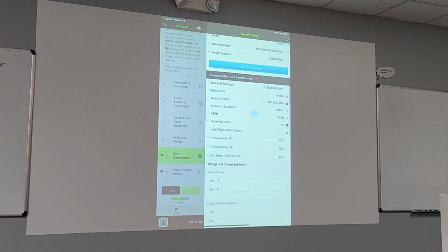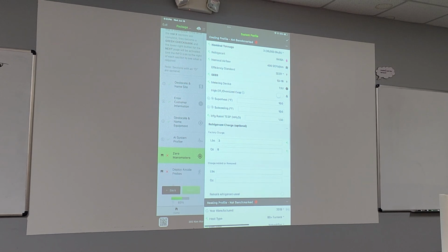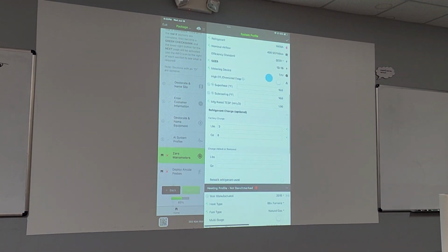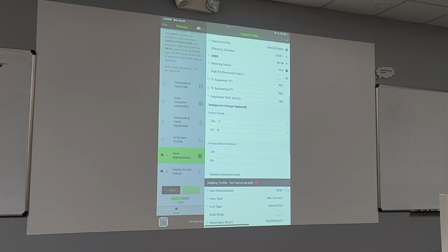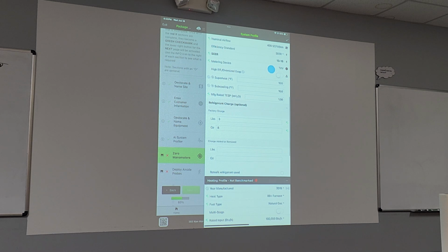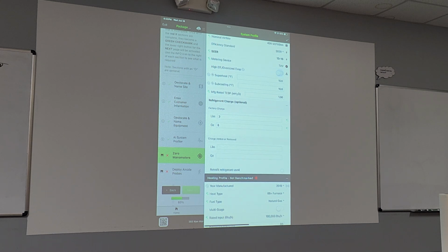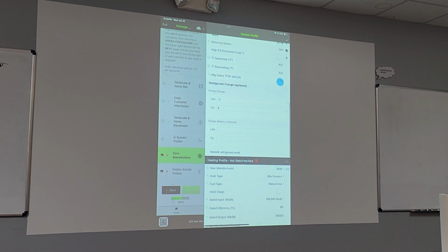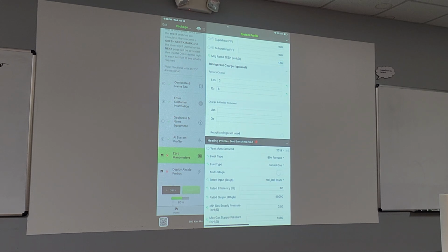The model number and serial number are all filled out from AI, and tonnage, and this is what I mean. We got to know what the metering device type is. We need to know what the SEER rating is. And if you tell it it's a TXV, we're scoring you based on subcooling. If you tell it it's a piston, now we're scoring your refrigerant charge based on superheat. Little switch right here for oversized evaporator. That tells it if you have an evaporator that's a half ton oversized to the condenser unit. It will not be able to compensate for something like a Carrier Infinity unit that has a crazy big 5-ton evaporator on a 3-ton condenser. It doesn't compensate that far. So superheat and subcooling targets, by default they're 10, but if you have any specs from the manufacturer, put that in here.